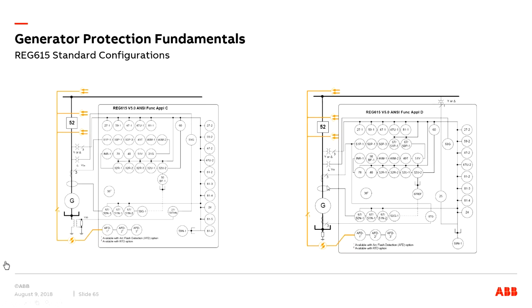So you can see here that we have two sets of CT only in this case, right? You have the neutral side CT and the terminal side CT, and this is the CT input which is used for all different types of protection. So we don't need a separate CT in addition to these differential protection CTs. This is a ground fault detection transformer here, which is used for detecting the ground faults. But other than that, there are no other CTs required in the modern protection relays. So I hope I have answered that question. But if you have still more, you can always send us an email to understand your situation better, and then we can definitely discuss that. Back to you, Nina.